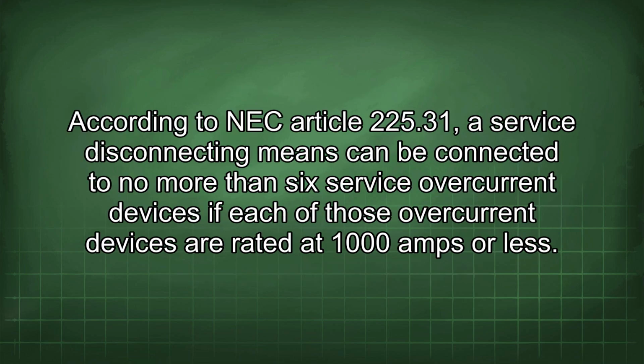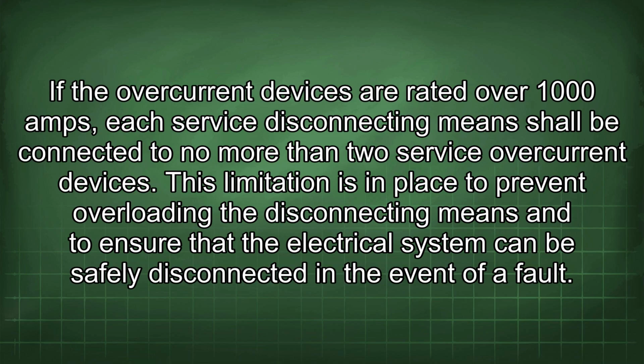According to NEC Article 225.31, a service disconnecting means can be connected to no more than 6 service overcurrent devices if each of those overcurrent devices are rated at 1000 amps or less. If the overcurrent devices are rated over 1000 amps, each service disconnecting means shall be connected to no more than 2 service overcurrent devices. This limitation is in place to prevent overloading the disconnecting means and to ensure that the electrical system can be safely disconnected in the event of a fault.